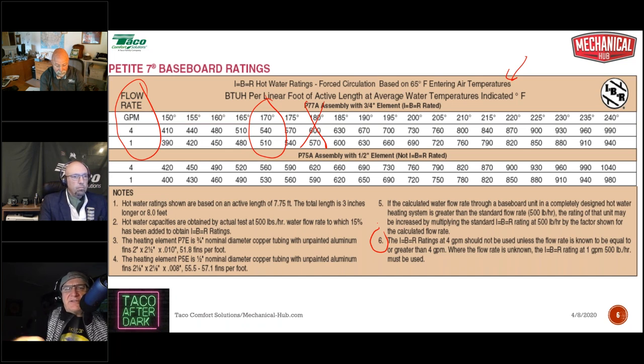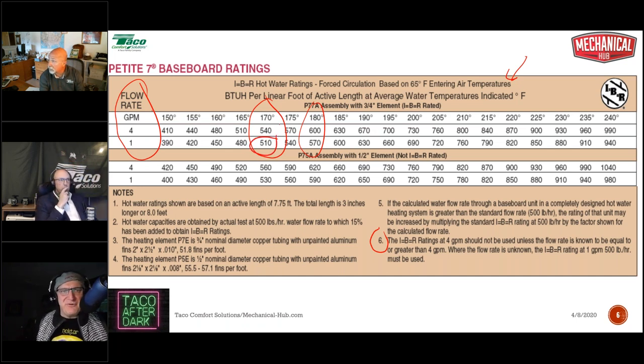So here, let's take a look at this. If we look at this the wrong way and we say, okay, 180 degrees, 600 BTUs per foot, that's darn good baseboard, I'm going to use that. I get more output at 180. I get 600 BTUs per foot. In reality, we really should be looking at this number, 510. All right, that's only 90 BTUs per foot. But another way of looking at it, that's about 20% less output per foot of baseboard. So you may not have an issue. This stuff tends to be fairly forgiving, but at least it's good to be precise and to know what it is you're looking at. Okay.